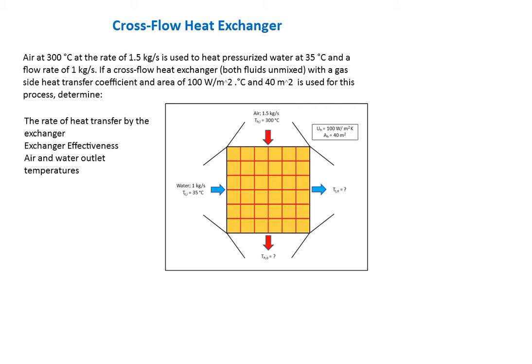In this example, we're going to look at air at 300 degrees Celsius at the rate of 1.5 kilograms per second that's used to heat up water at 35 degrees C and a flow rate of 1 kilogram per second. We have a cross flow heat exchanger with both fluids unmixed, a gas side heat transfer coefficient of 100 watts per meter squared C, and an area of 40 meters squared. We want to determine the rate of heat transfer, the effectiveness, and the air and water outlet temperatures.